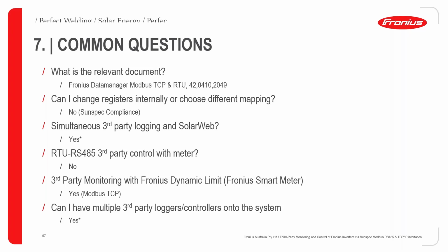Whenever devices are being polled by more than one, two, three, or more than five loggers, let's say, and the data request is substantial, remember, slaves will be busy responding to the initial request before they take the second request. So when you start implementing this third-party control and logic, a bit of thought needs to be put in place. What comes first?